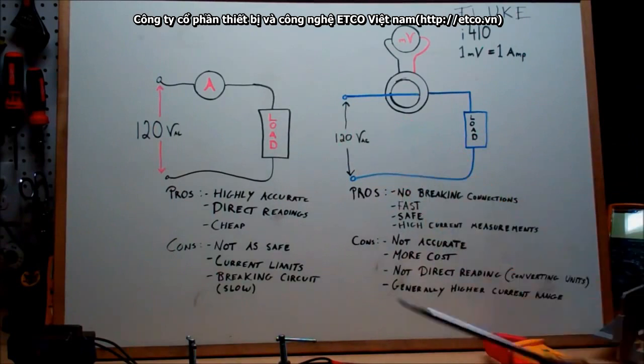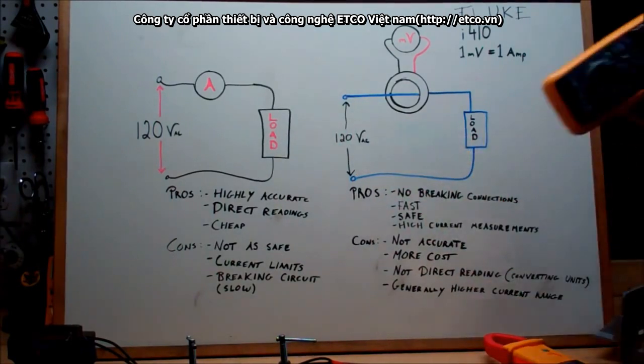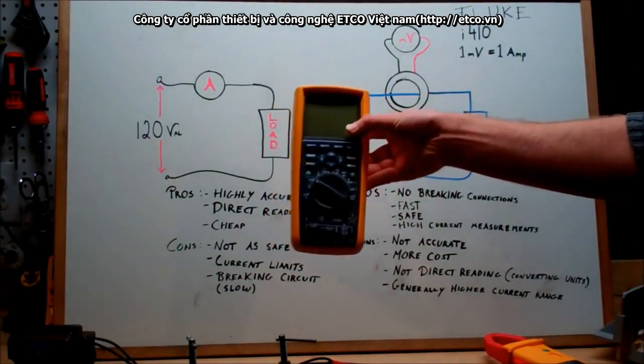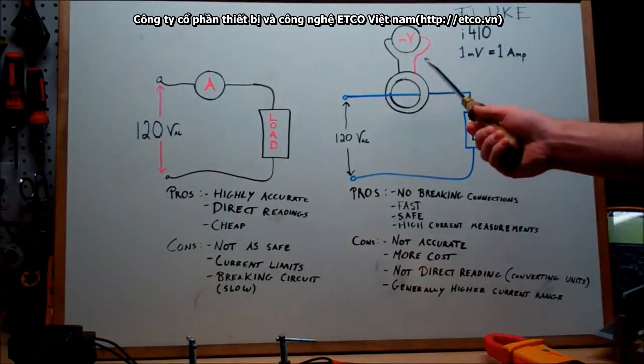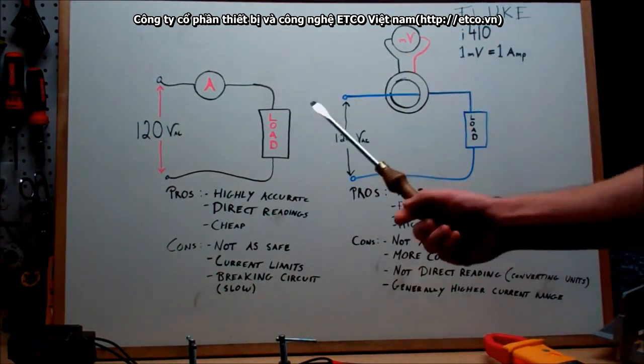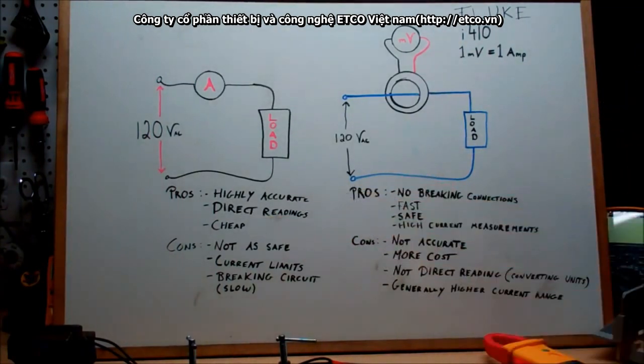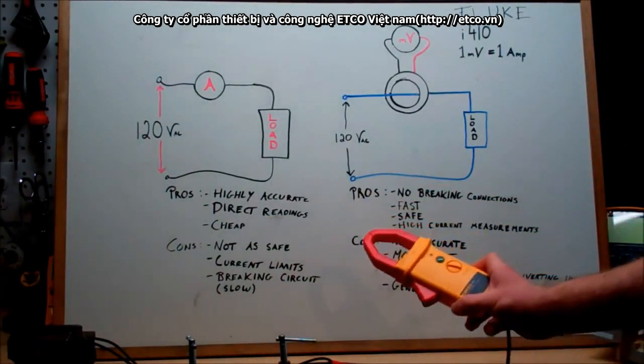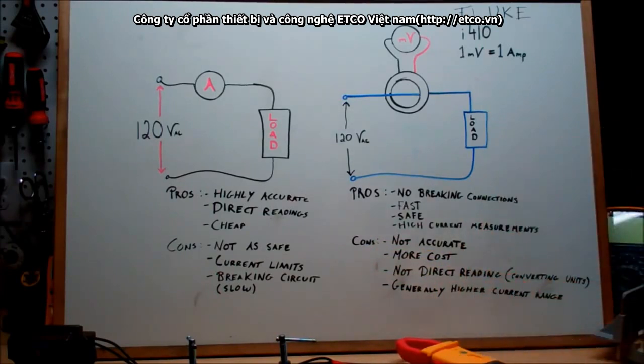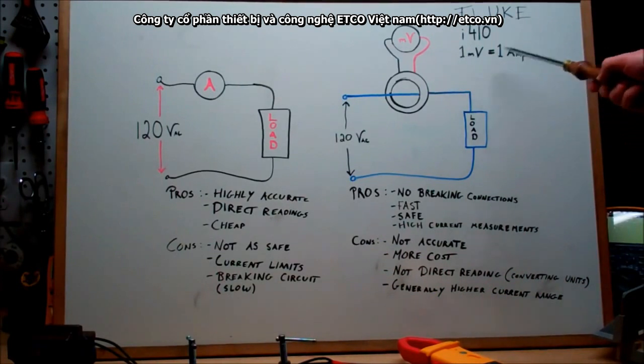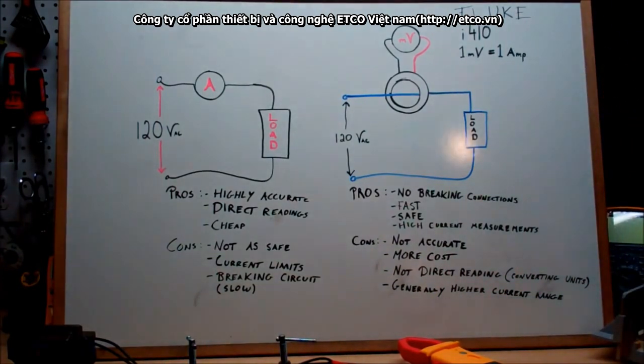First off, highly accurate. When you're using something like your Fluke 289 here, you get monstrous results for accuracy. Where if you use something like your current meter, your results aren't as accurate. Now you also get direct readings. And what I mean is when you're using a clamp meter, you don't have a direct current reading. You get a translation. And what I mean is you get millivolts. And for the current meter I'm using, 1 millivolt equals 1 amp. And that is a really nice friendly ratio to work with, but not all of them have that ratio. Next is the cheapness. This is a pretty decently cheap setup for high accuracy.